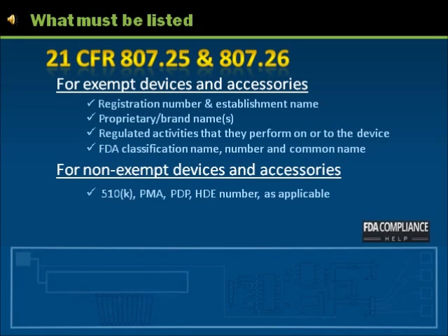Devices having variations in physical characteristics such as size, package, shape, color, or composition should be considered to be one device, provided the variation does not change the function or intended use of the device. Owner-operators can satisfy the identification name requirement by submitting the product code for all listed devices that are exempt from pre-market notification and approval, or the product code for devices put into commercial distribution prior to 1976, unless the effective date for the requirement of pre-market approval has been established.